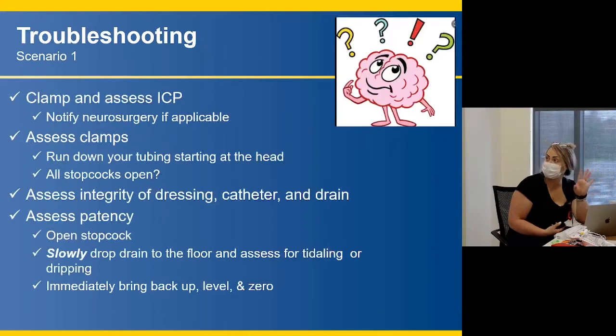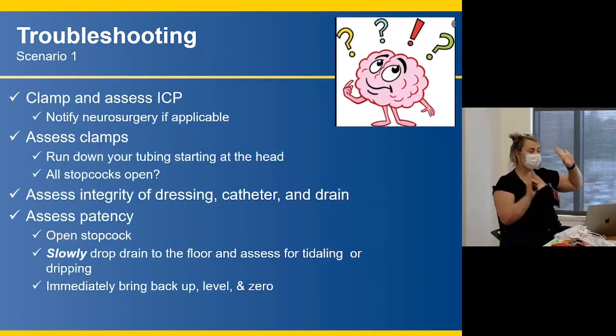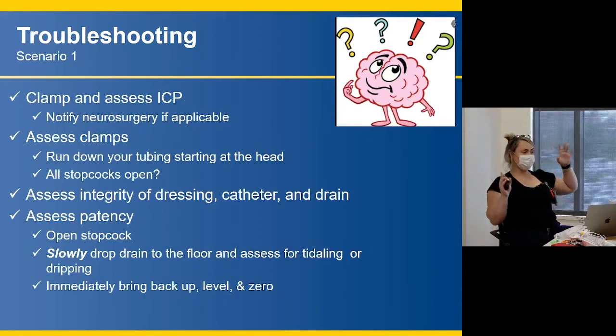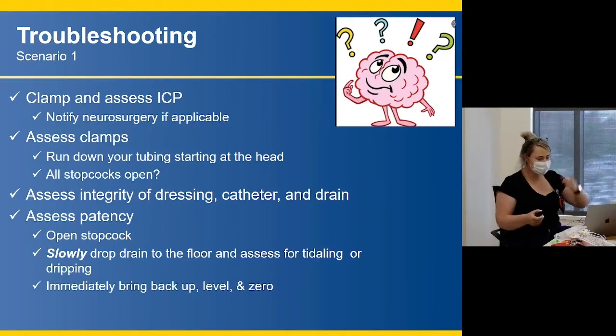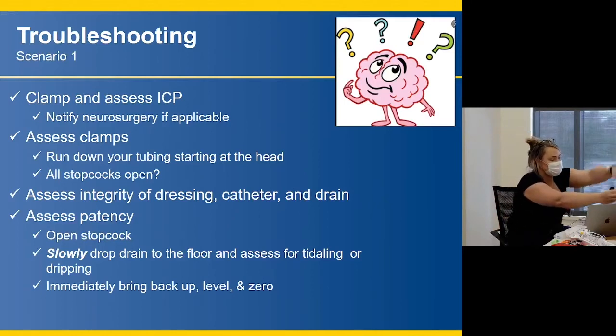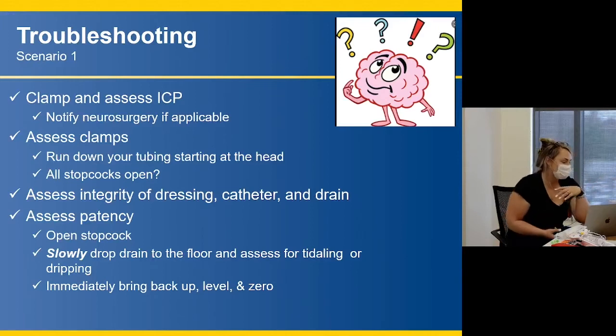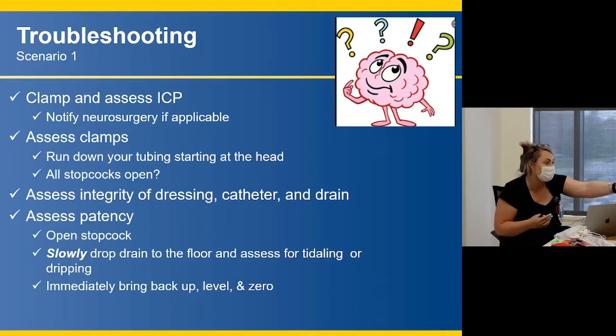Assess your clamp. What I like to do is just run down, just like you would your vent tubing. If something is disconnected, run down from the head. So you're going to check that clamp at the head, you're going to check this little slide clamp, and you're just going to go down and make sure nothing is kinked and everything is open and patent. Especially if someone transports for you, their practice might be to clamp off at the head. I know Lifeline did that sometimes downtown. So just, again, be mindful and run down the system.